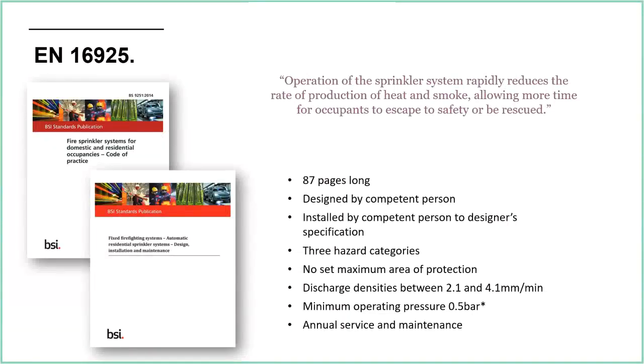EN 16925 has similar ideas: competent person, designed to designer specification, three hazard categories. There's no set maximum area of protection — that's down to the manufacturers of the sprinkler heads. Discharge density is between 2.1 and 4.1 mm per minute, and minimum operating pressure is half a bar, again largely down to the manufacturer's instructions. Annual service and maintenance is also required.